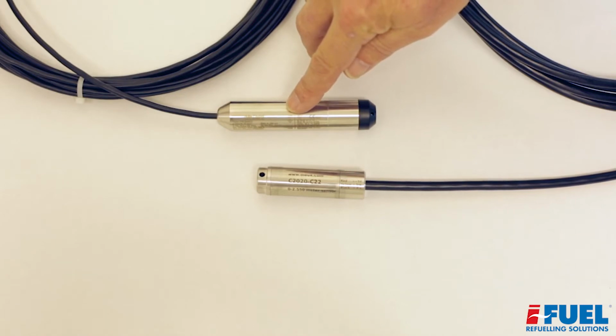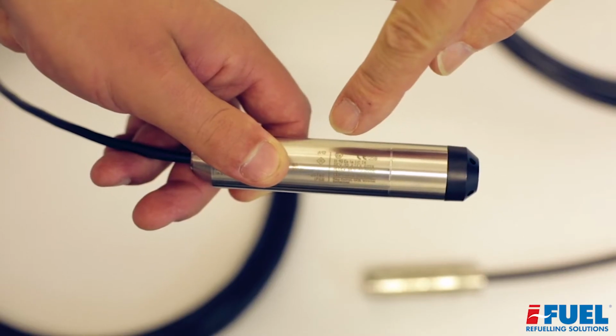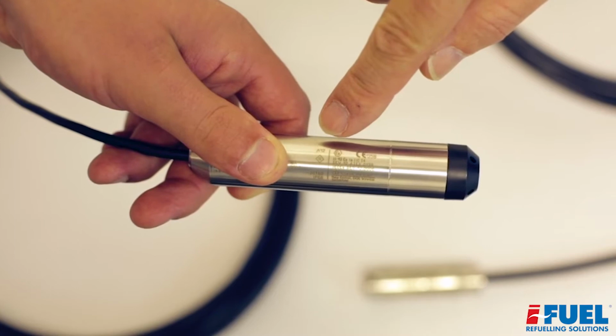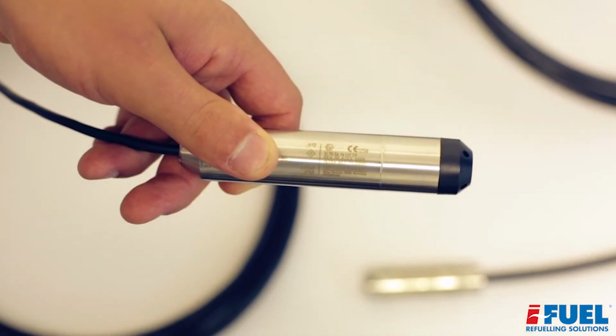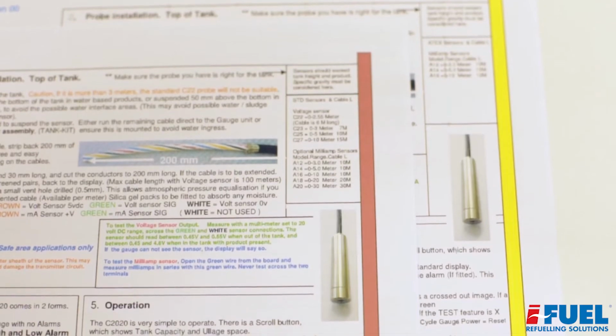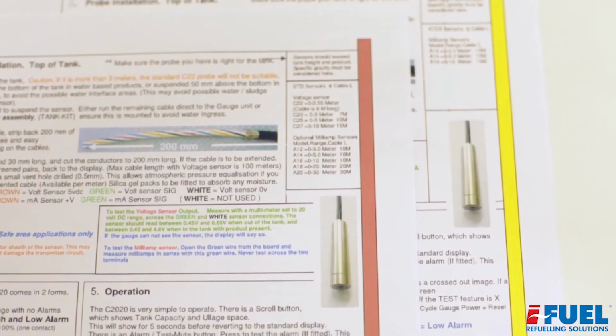There is a code etched on the sensor, or if this was purchased as a complete kit, the last section of the kit box part number defines the probe range. Check this suits the tank height. Cross-references are shown in the IO manual.